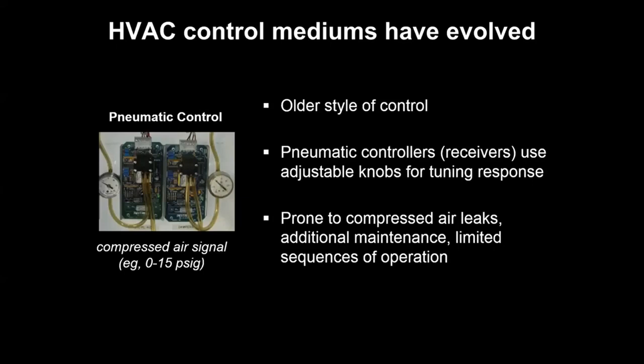And these controllers or receivers have knobs so that you can adjust the control response associated with different elements in your system. So the problem here, because it's not all bad, I think a lot of maintenance folks would say that it's less black boxy than some of our digital controllers, where once you understand how these systems work, what you see is what you get. And you have all the knobs right at your disposal so you can adjust the system to stage it and adjust the control how you need to.